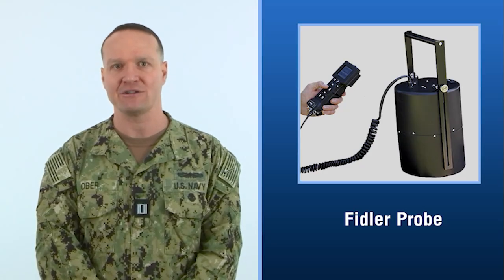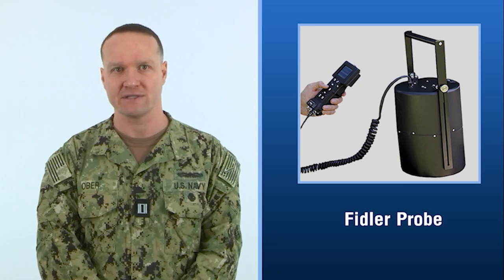The GPS interface uses GPS Standard Serial Interface Protocol to add GPS information to data files collected by the base unit. The base unit also measures both low-energy beta radiation and photon radiation. It can measure alpha, beta, photon, and neutron radiation depending on the probe attached. When the field instrument for the detection of low-energy radiation, or FIDLER probe, is attached, some discrimination is available to allow the user to identify the likelihood of certain nuclear materials being present.